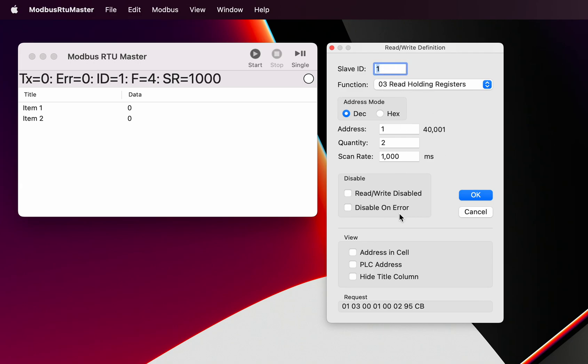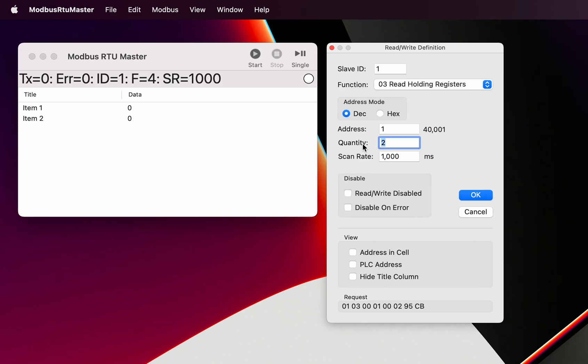Down here we can actually see the bytes that are being sent to the Modbus slave. If you are familiar with the Modbus protocol, you can see that's the slave, that's the function, the Modbus function, that's the starting address, that's the register quantity, and that's a checksum. As you're changing what you enter in here, you can see the change down here happening as well.